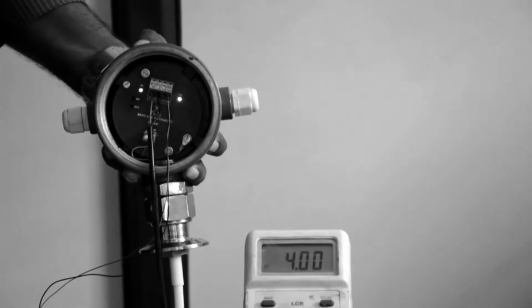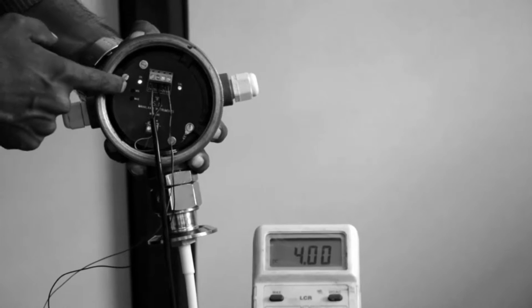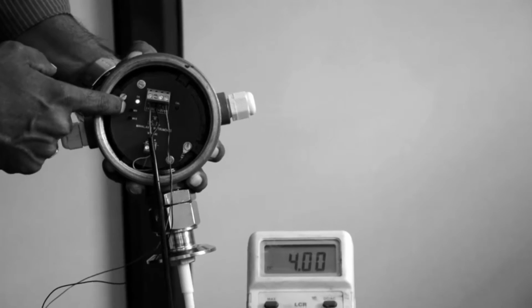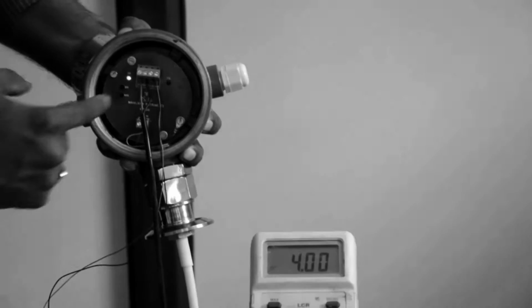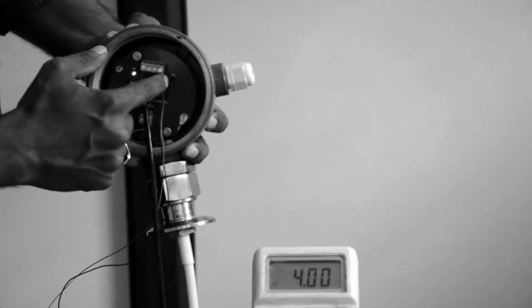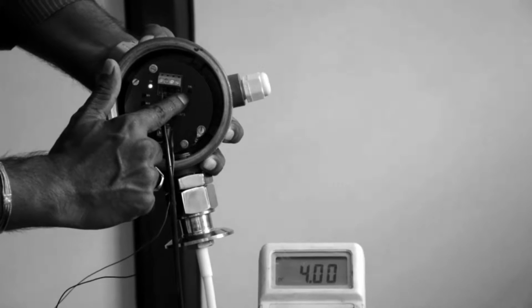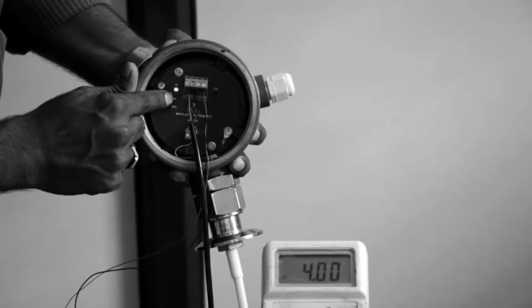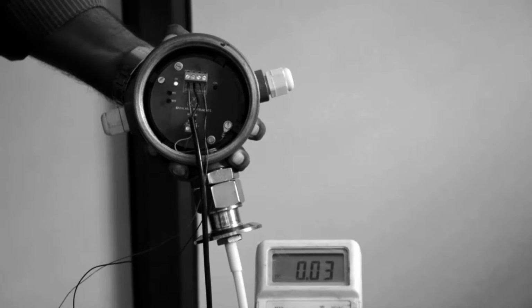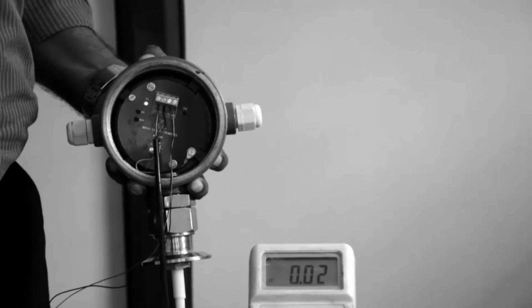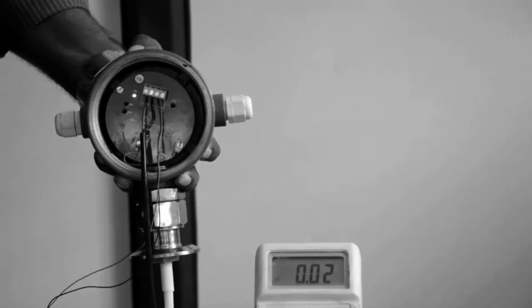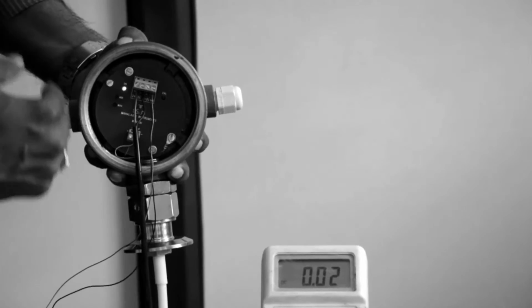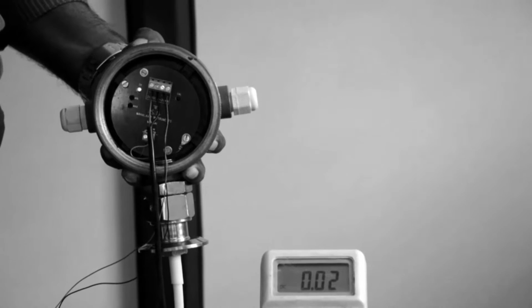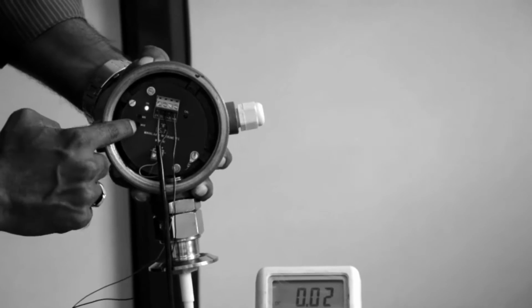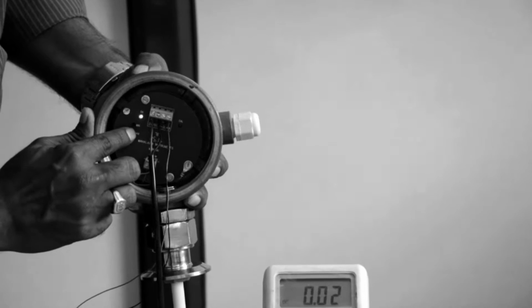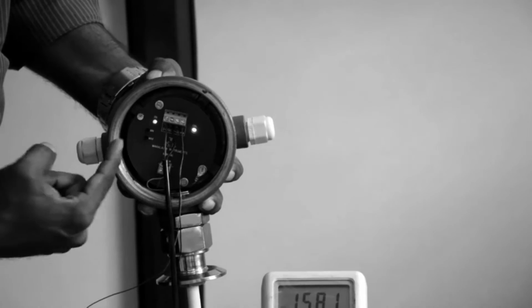It's a perfect 4. So since this is perfect 4, I'm going to again press the minimum push button for 3 seconds so that our instrument comes out of the 4 milliamps calibration, and you can see that the calibration LED has stopped blinking. So we have come out of the 4 milliamps calibration. Now what we are going to do is we are going to do a 20 milliamps current calibration. So I'm going to press the maximum push button for 3 seconds.